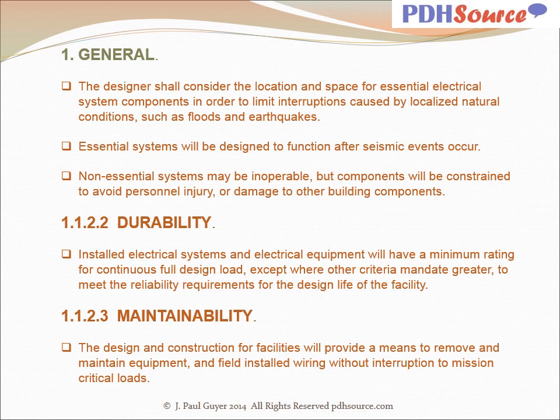Installed electrical systems and electrical equipment will have a minimum rating for continuous full design load, except where other criteria mandate greater to meet reliability requirements for the design life of the facility. The design and construction for facilities will provide a means to remove and maintain equipment and field installed wiring without interruption to mission critical loads.